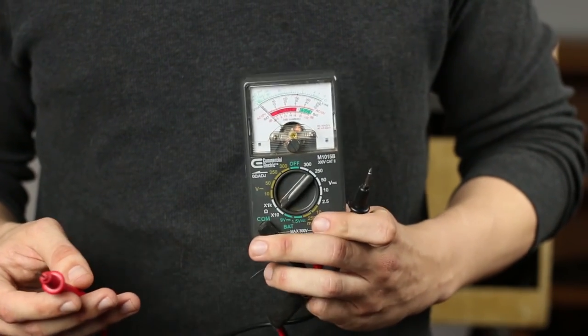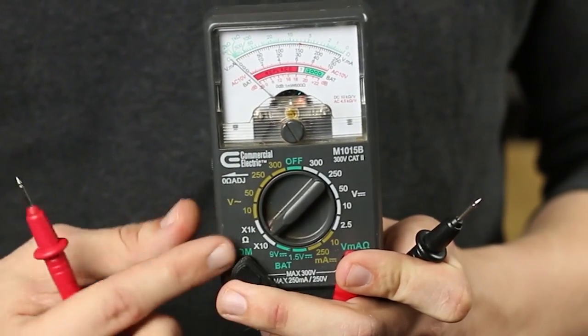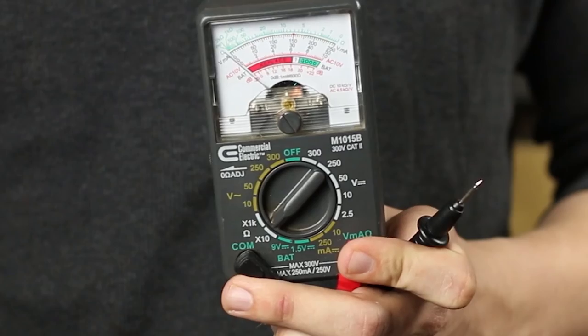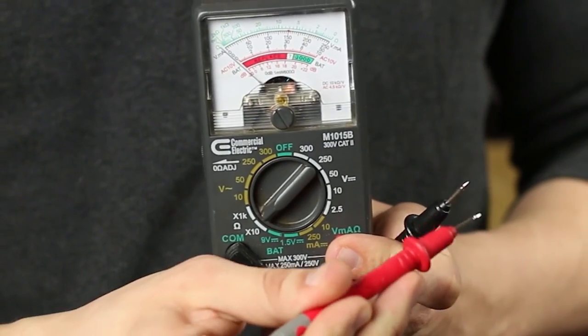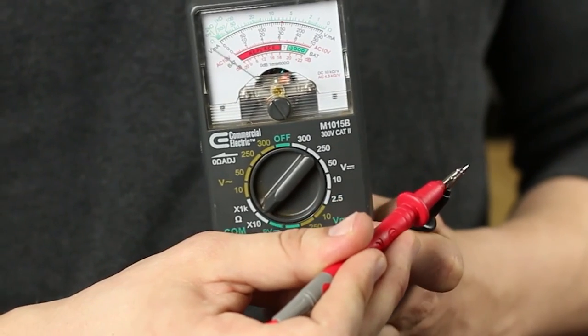To test if your equipment is properly grounded, we're going to use a multimeter. Set it to test for continuity — that's often represented by the Omega symbol. This means that any time there is continuity between the red and the black probe, the needle will jump.